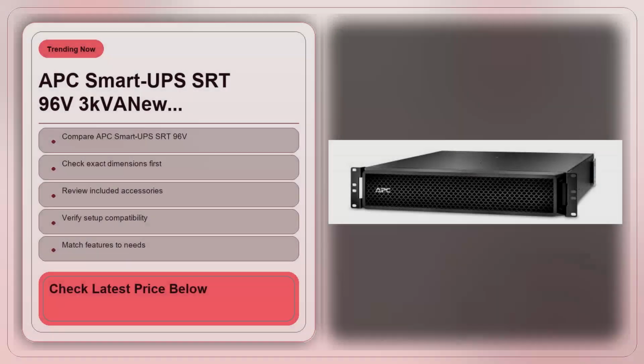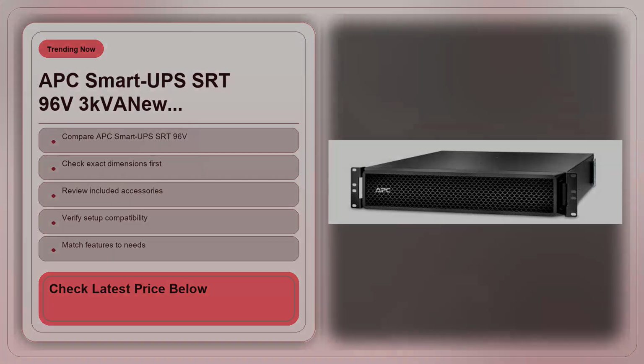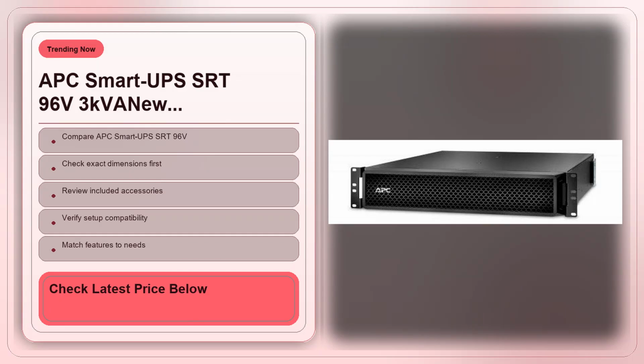Another aspect that often trips up new buyers is the UPS's communication interface. The SRT series ships with a network card that lets you monitor power health, battery status, and load levels through APC's PowerChute software or a web UI. That's a big advantage if you have multiple devices to manage, you can set up email alerts for low battery, schedule graceful shutdown scripts, or even integrate the UPS into a larger monitoring platform like Zabbix. But the software can be a bit finicky on newer versions of Windows or Linux, requiring you to tweak driver settings or apply firmware updates. If you're not comfortable diving into network configurations, you might end up with a UPS that sits there quietly, while the real-time alerts you hoped for never appear.